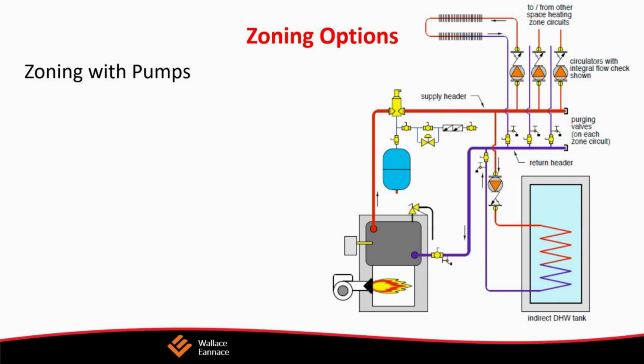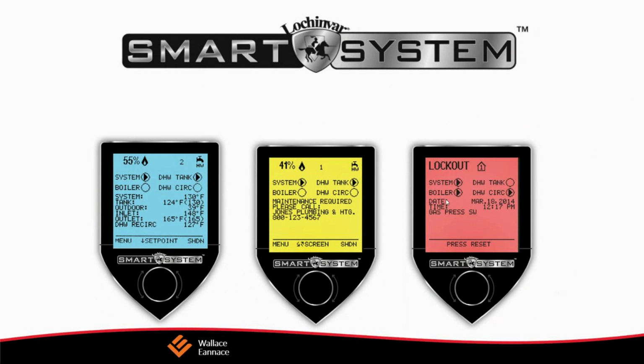Another option, which I find done in many applications, especially radiant heating applications, is to zone by circulator. Usually they use a control box where they wire the thermostats, and it turns the pumps on and off for each zone. They can be either high temperature or a secondary temperature. One of the advantages of Lochinvar boilers is that when you have multiple temperatures like that, you can set a different reset curve for each of those different water temperatures.